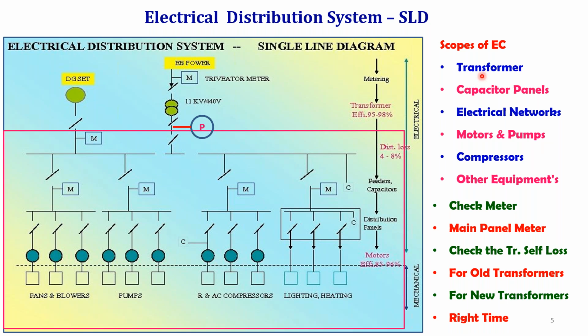Now there is scope for all types of equipment. We can have scope for energy conservation in the transformer, capacitor panels, electrical network, motor and pump system, compressor, and other equipment. So if you open your eyes when you want to conserve energy, then automatically a lot of scope is available. Even most of the veterans will say that there is always scope for improvement. So you will always look for where the scope for energy conservation proposals is. And similarly, you always think about what the design value is and what the operating value is. If you compare the operating value with the design value, then automatically you can come to a conclusion about what areas you can improve.